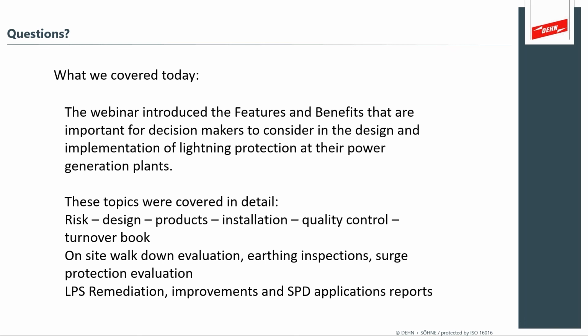One thing to also mention is that the natural components of a facility can also be used as natural air termination. There's also Table 3 in the standard that addresses the minimum thicknesses for these types of natural air termination systems. We need to take into consideration that if using these as natural air termination systems, you can get a direct strike on these structures. If you don't comply with these requirements, you can get hot spots or even puncture or penetration of the lightning current. That's why we also like to install the air termination system and bond it to the natural steelwork. That lifts the coverage a bit higher and provides a point of attachment, and we make sure that point of attachment is an air termination rod that has been tested to handle the initial charge and energy when lightning connects to it. Then we make sure of the electrical continuity of the natural steelwork in those settings.